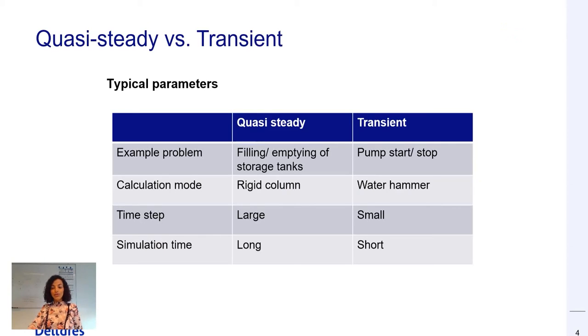When a valve closes too quickly or a pump shuts down suddenly, a hydraulic shock is generated in the system. This phenomenon is also called water hammer and it describes the momentary rise in the fluid pressure in a piping system when the fluid suddenly stops.